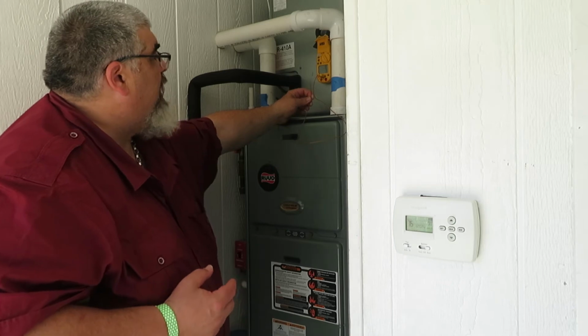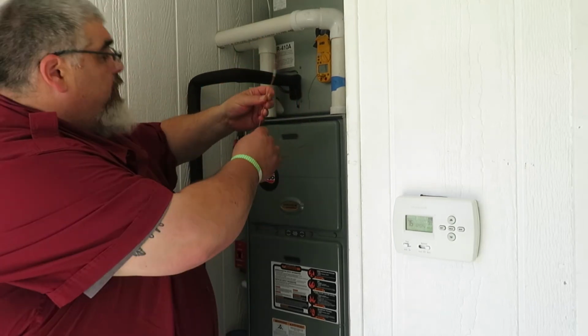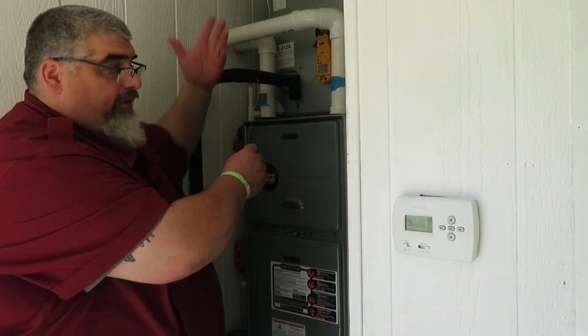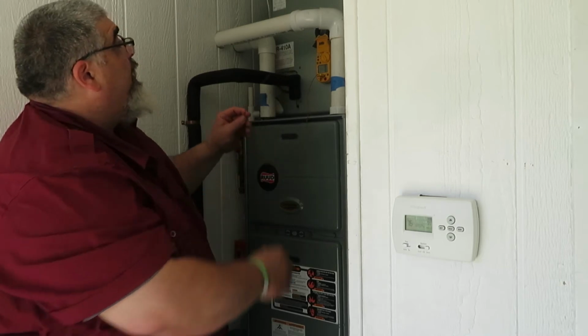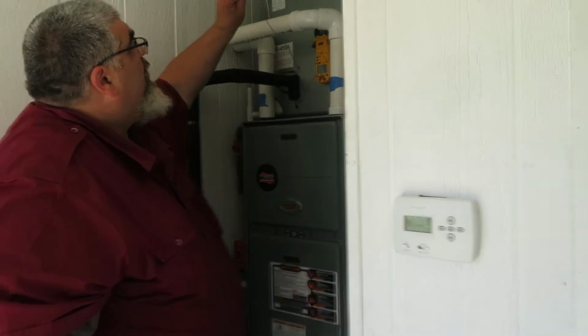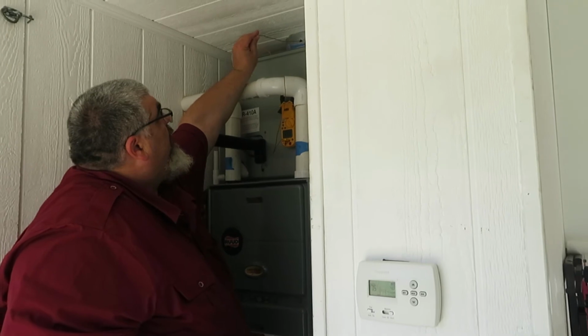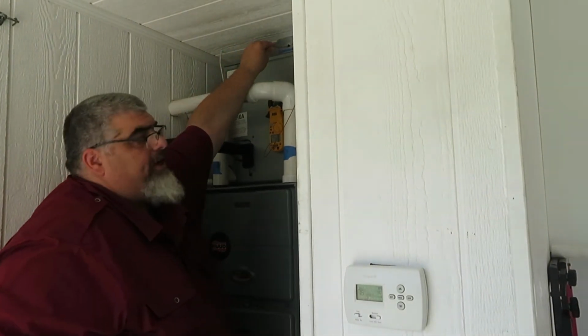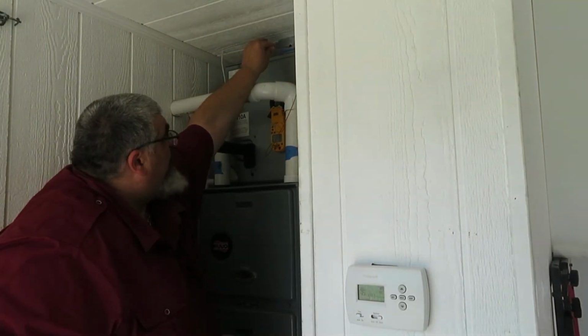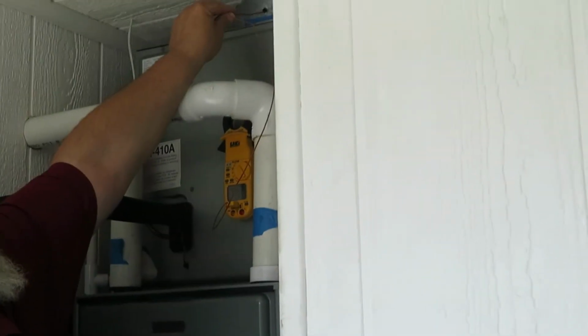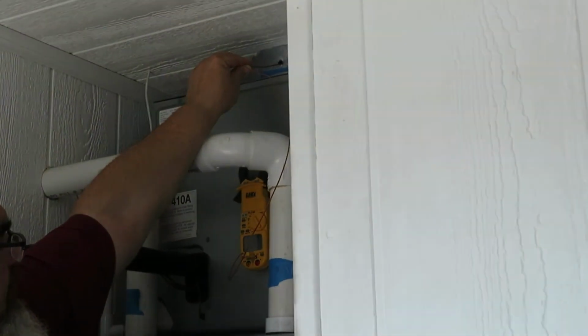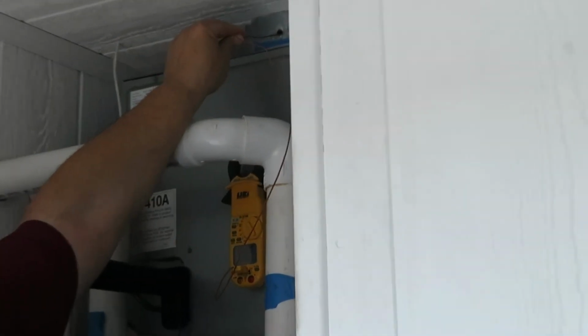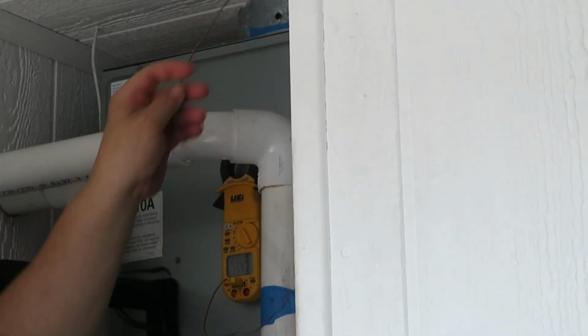So to do a temperature rise test, you take your thermometer. You can do the return or the supply first. It doesn't really matter. I usually like to do the supply first. All we're going to do is stick our probe into the ductwork in the center. We're going to hold it there, and we'll try to wait until the temperature kind of steadies itself out a little bit. Looks like at about 160.5 degrees.